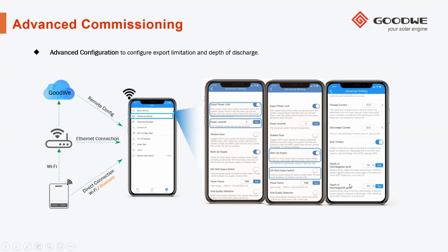And then lastly, at the bottom, we've got our depth of discharge on-grid and our depth of discharge off-grid. You'll see also our grid quality detection, and we have low sensitivity as well. The grid quality detection is always recommended to put on, because without that, you won't have your quick changeover time.